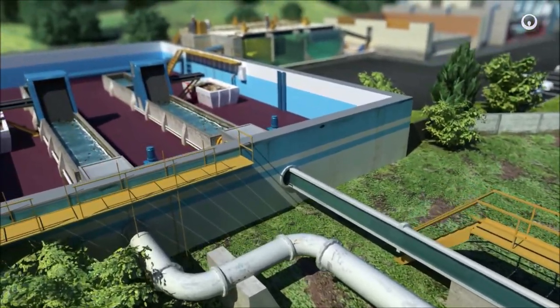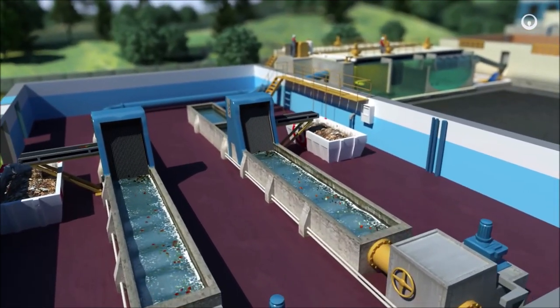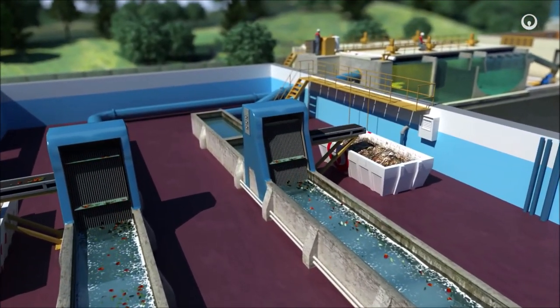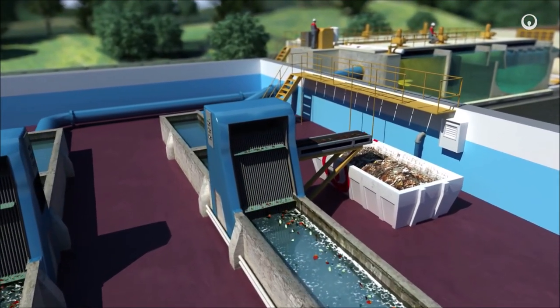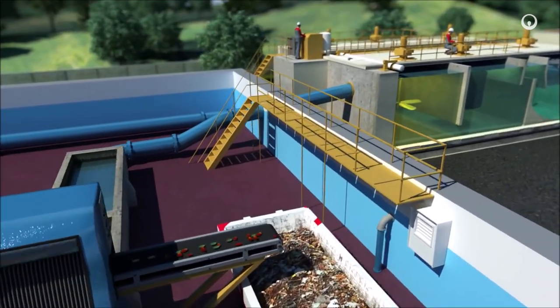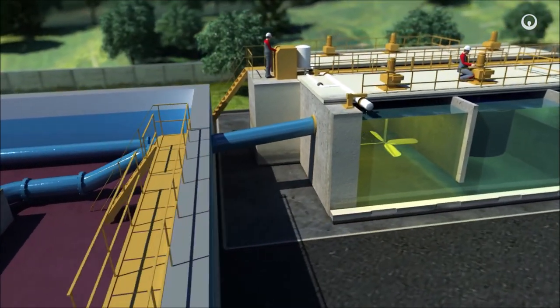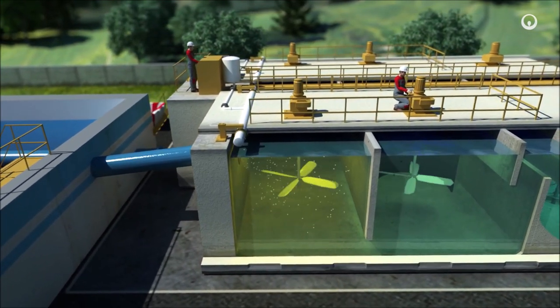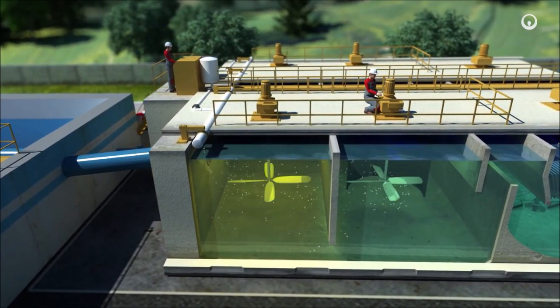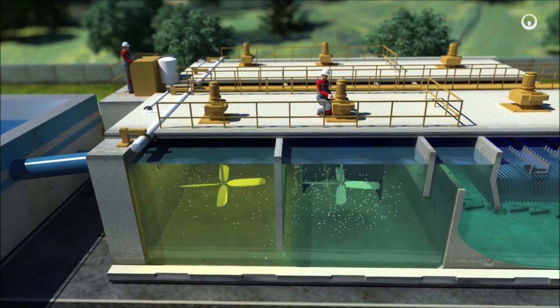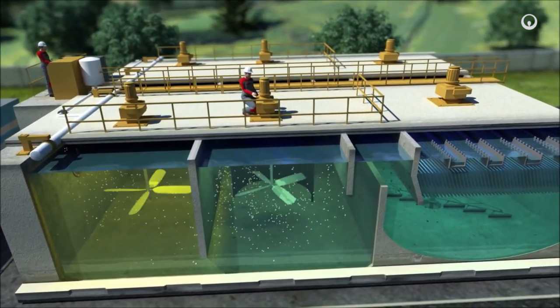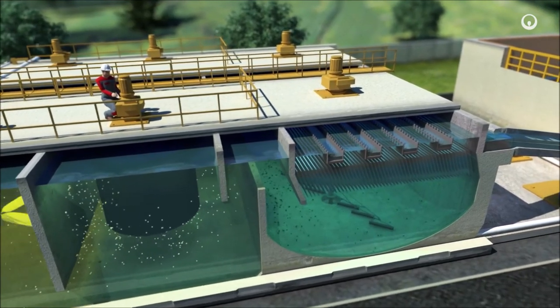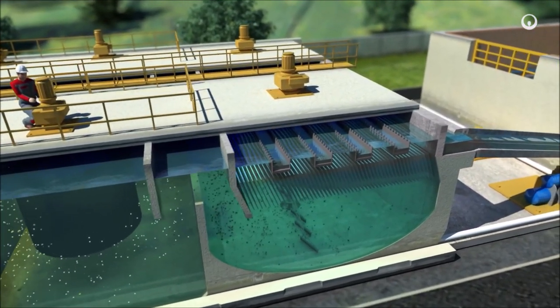First, we remove the suspended matter in the water. Here, screens block the solid waste and rakes then lift it out. Then we add a coagulant to the water. The dust, soil particles and other residual material gradually combine into clots, which are called flocs. Gravity drags these flocs to the floor of a large settling pond and we remove them.